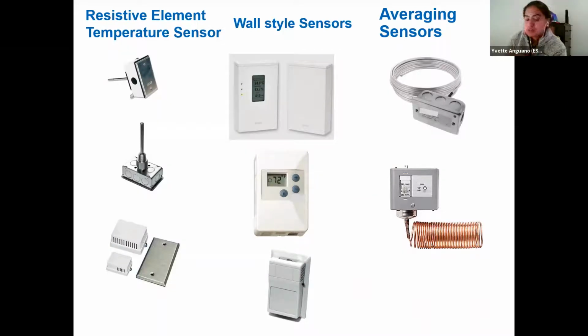Some of these sensors may also be combination sensors. So in addition to the temperature sensing element, they'd have a CO2 or humidity combination, which would be tied to the terminal unit in the space, and can also cause an override to the control to pull in more fresh air into the space, regardless of the current temperature, as a reaction to increased CO2 in the space. So we've got to put that specific detail in our specifications to ensure that our clients get what they want or what they need due to code in that space. So just to reiterate that.